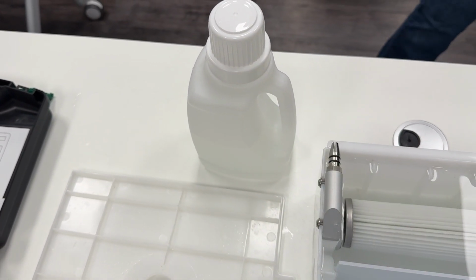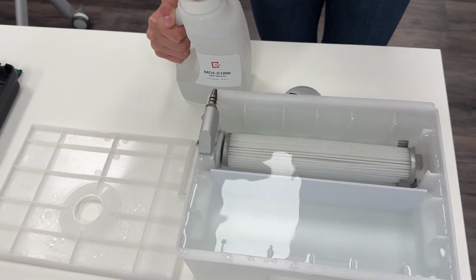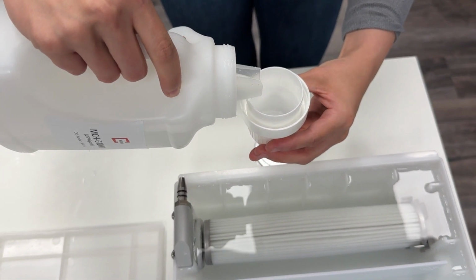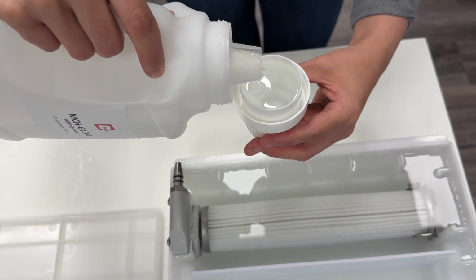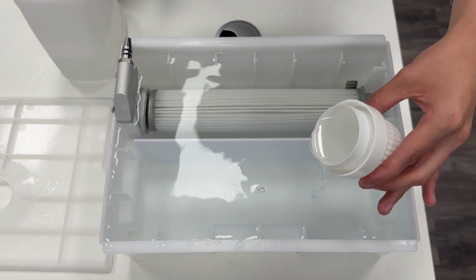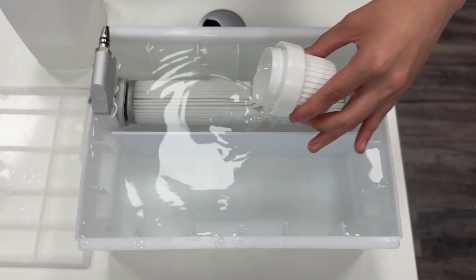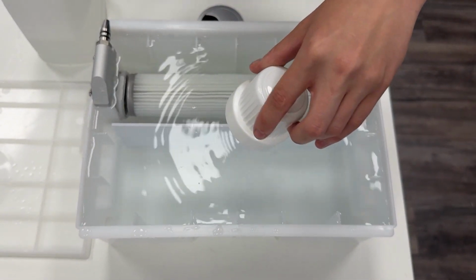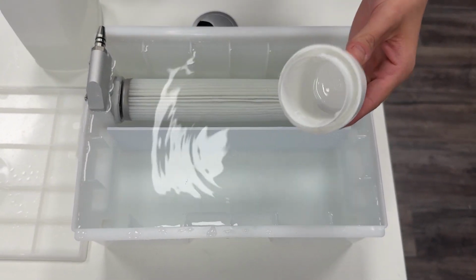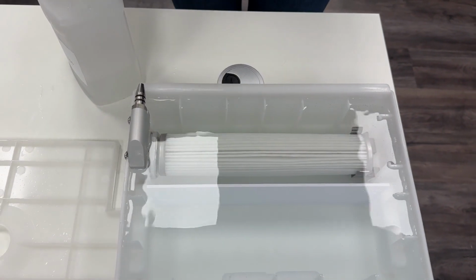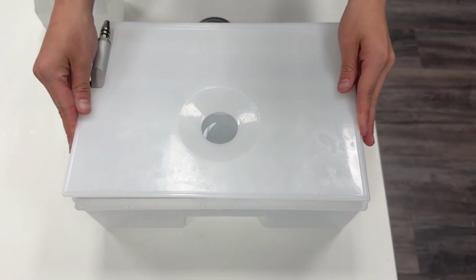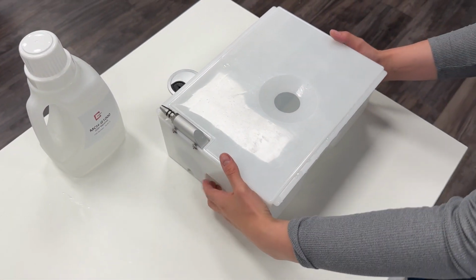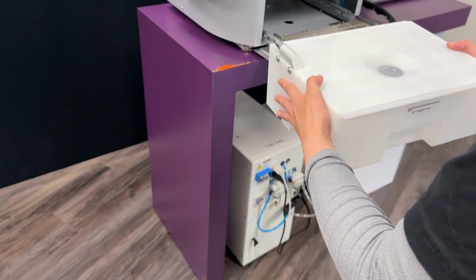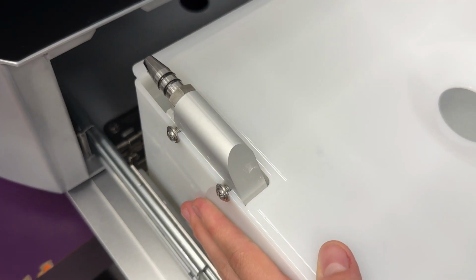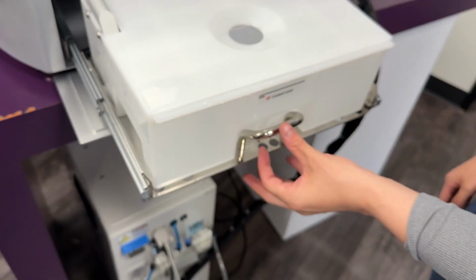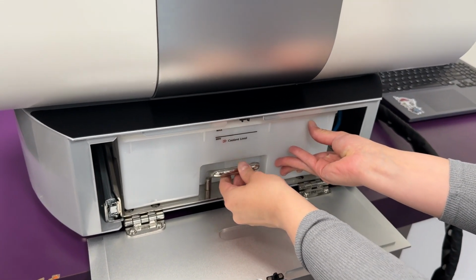So the last step here is to use the lubricating liquid. We're going to use one full cap of this liquid in the 4,000 milliliters of water. And when I say full cap, it's pretty full, right up to the top. Okay, and from there we can just put the cover back on and then bring it back over to the machine. You can set it right down on the tray here on the left hand side. You can see where it seats, and just press it all the way into the machine and close the door.